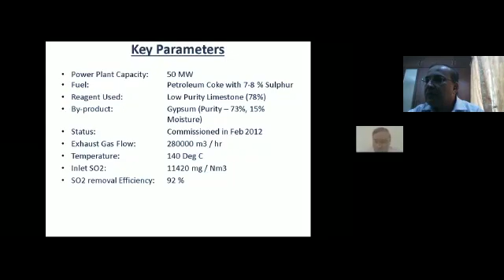The exhaust gas being treated is 280,000 meter cube per hour. Exhaust temperature is 140 degrees. Inlet sulfur, you see this because of using pet coke. The sulfur dioxide level itself is 11,420 milligram per normal meter cube. This FGD which was commissioned has 92% efficiency. It has drastically reduced the sulfur dioxide levels. The electrical consumption for this itself is 950 kW, almost nearing 1 megawatt.